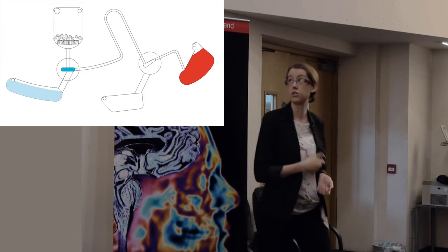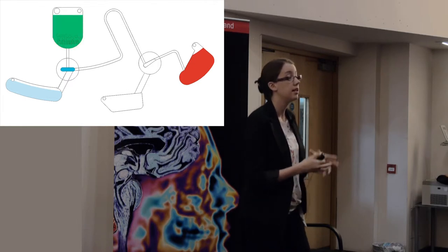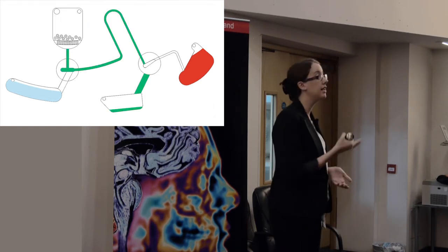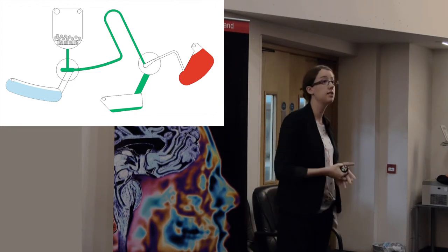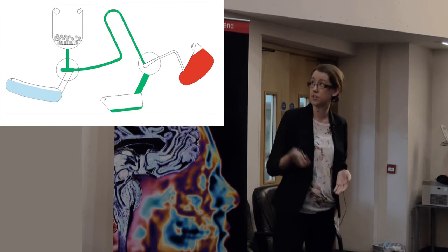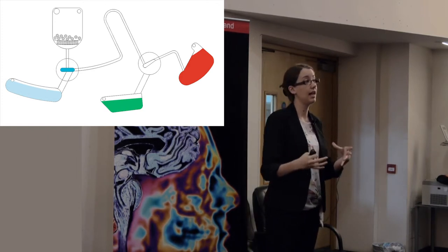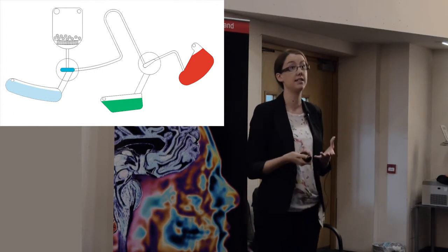Your second organic solution follows the same path. Finally you add water - the RNA unbinds from the now-clean beads and resuspends in the water. Once flowing, it passes through the hydrophobic membrane and travels over the siphon, but now the dissolvable film has been dissolved away in the first stage, so it collects in chamber three: a completely uncontaminated sample ready for detection and analysis.